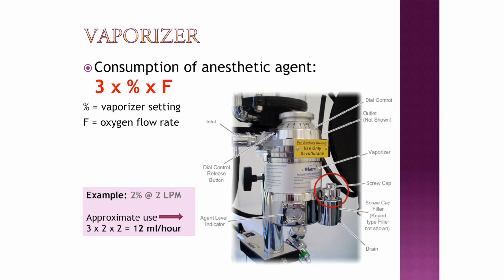A lot of times, the cap to this is actually the key. So if you pull the cap up, flip it upside down, you can tighten that up so it's not leaking, or you can call me and I can do it. But most of the time, these vaporizer caps do serve as a key for in there. Always wash your hands after you handle liquid anesthetics because they can get absorbed through your skin. So even if you're filling the vaporizers at the end of the day, just make sure you wash your hands after that.